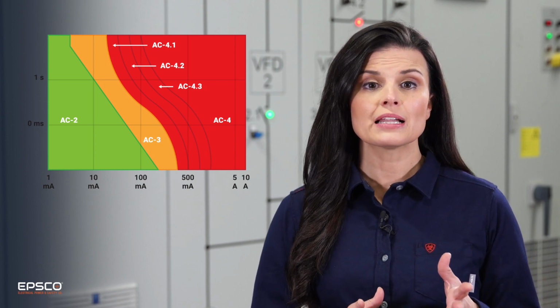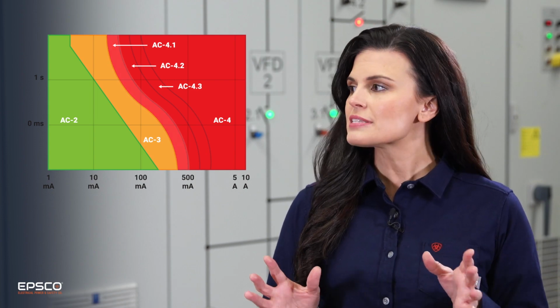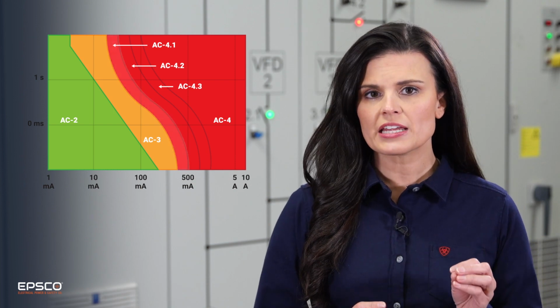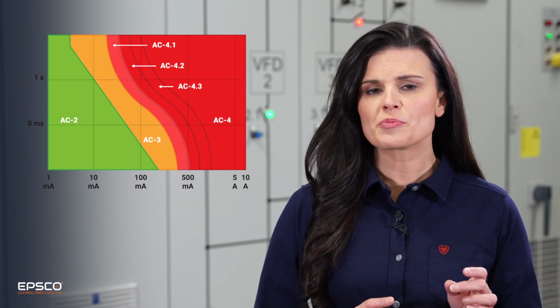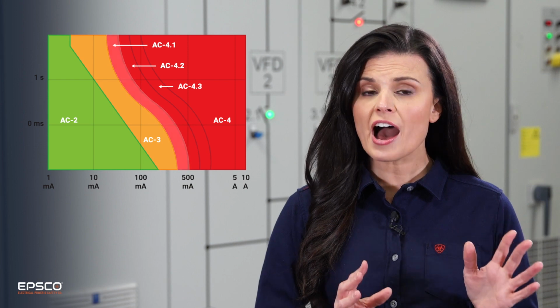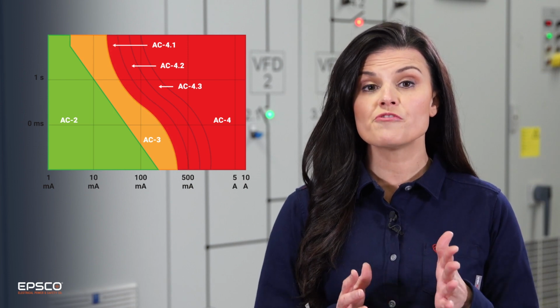Using the 500 milliamps from our example, you can see that after just 1 second of connection, the likelihood of heart fibrillation increases from just 5% to over 50%. Remember, it only takes 5 milliamps before you can't voluntarily let go. If you're working on 480 volts and become part of a circuit, you're almost 100 times over the let-go threshold.